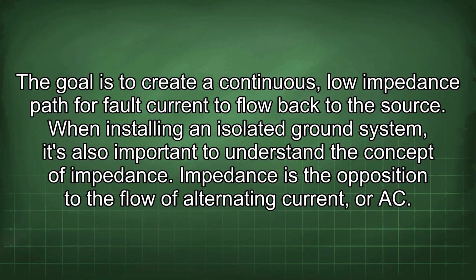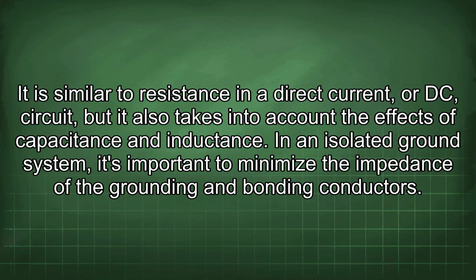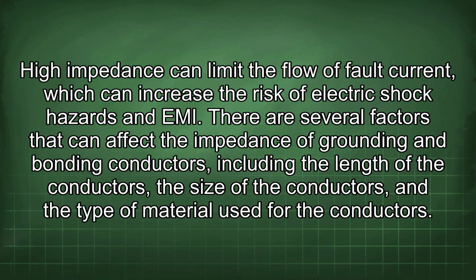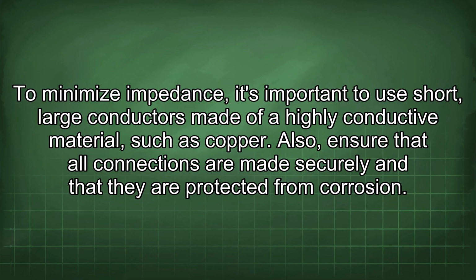When installing an isolated ground system, it's also important to understand the concept of impedance. Impedance is the opposition to the flow of alternating current, or AC. It is similar to resistance in a direct current, or DC, circuit, but it also takes into account the effects of capacitance and inductance. In an isolated ground system, it's important to minimize the impedance of the grounding and bonding conductors. High impedance can limit the flow of fault current, which can increase the risk of electric shock hazards and EMI. There are several factors that can affect the impedance of grounding and bonding conductors, including the length of the conductors, the size of the conductors, and the type of material used for the conductors. To minimize impedance, it's important to use short, large conductors made of a highly conductive material, such as copper. Also, ensure that all connections are made securely and that they're protected from corrosion.